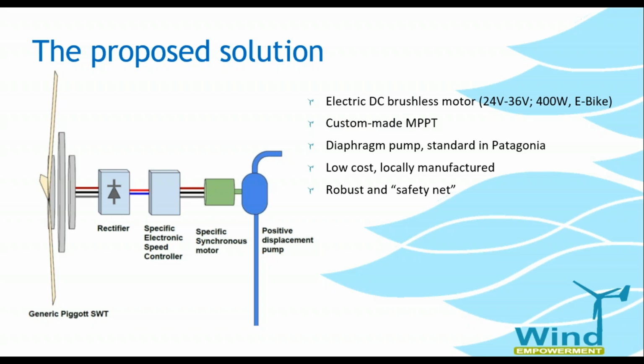And there is this custom-made MPPT, which is the key factor of the whole system. It will convert the DC generated by the wind turbine into DC for the motor, so that the motor will be operating at the frequency based on the wind speed of every instance. So it has to change very quickly. As the wind changes, the pump speed and the motor speed feeding the pump will be changing very quickly.